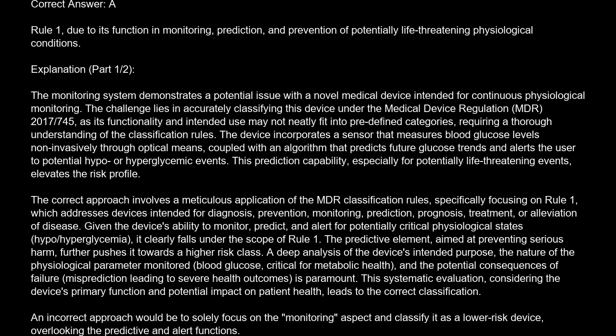The correct answer is A, Rule 1, due to its function in monitoring, prediction, and prevention of potentially life-threatening physiological conditions. Explanation: the monitoring system demonstrates a potential issue with a novel medical device intended for continuous physiological monitoring. The challenge lies in accurately classifying this device under the Medical Device Regulation, MDR 2017/745, as its functionality and intended use may not neatly fit into predefined categories, requiring a thorough understanding of the classification rules. The device incorporates a sensor that measures blood glucose levels non-invasively through optical means, coupled with an algorithm that predicts future glucose trends and alerts the user to potential hypo or hyperglycemic events. This prediction capability, especially for potentially life-threatening events, elevates the risk profile.